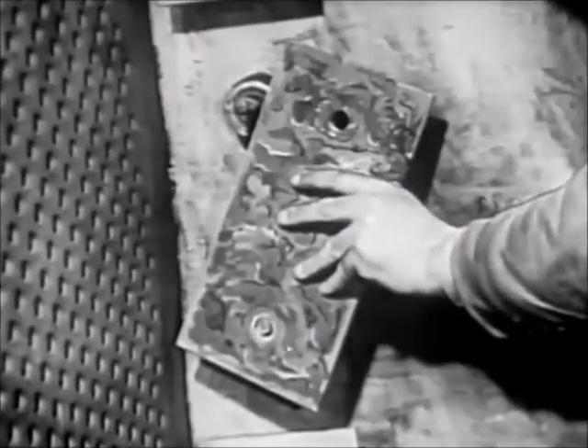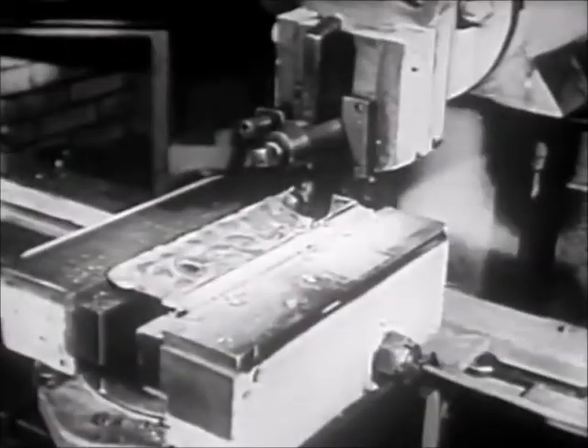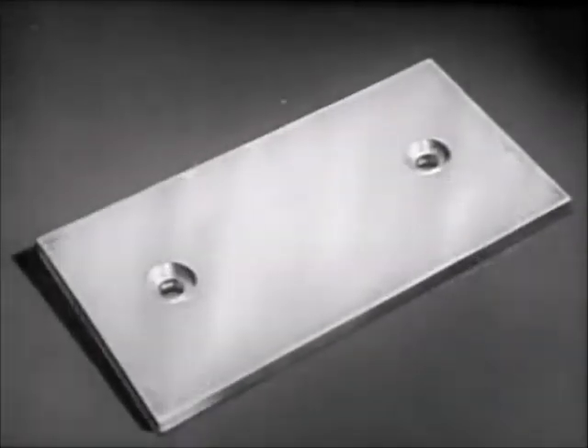For zinc maintenance, remove the zinc from its mount and chip off the scale, or machine it off. If more than half the zinc has been disintegrated, discard it and get a new one. When you replace the zinc, be sure there's good metal-to-metal contact with the zinc support.